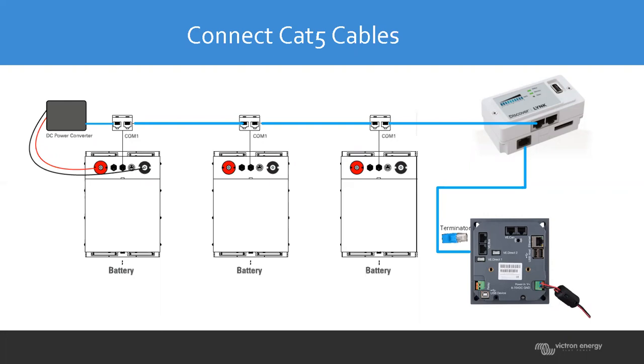With CAN bus, you'll need a terminator on the open slot. VE bus does not require that, but VE CAN does. The DC power converter and the Lynk device are internally terminated, so you don't have to worry about that.